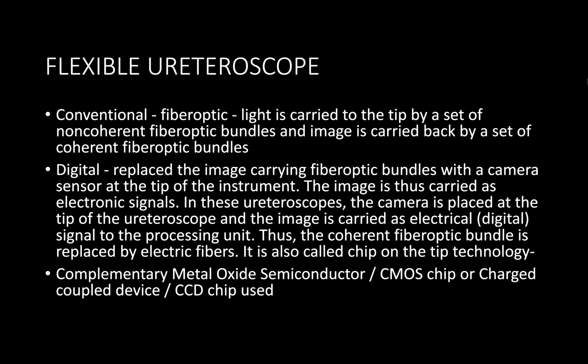Okay. How does the flexible ureteroscope work? A flexible ureteroscope is 70 to 80 centimeters long. It works on the principle of fiber optics. The fiber optic bundles are non-coherent within the light lead, so they don't have the same arrangement, but they have to be coherent, with the same arrangement at the distal and the proximal end, in order to produce the same image that's received.